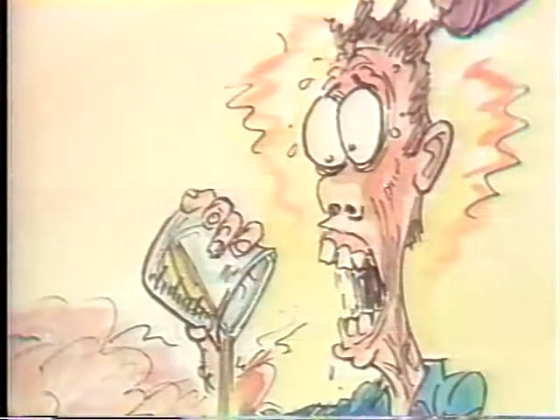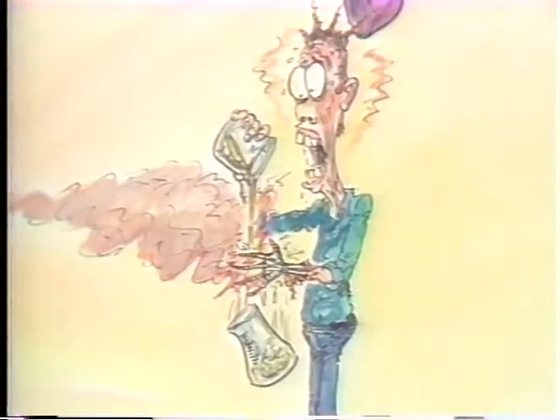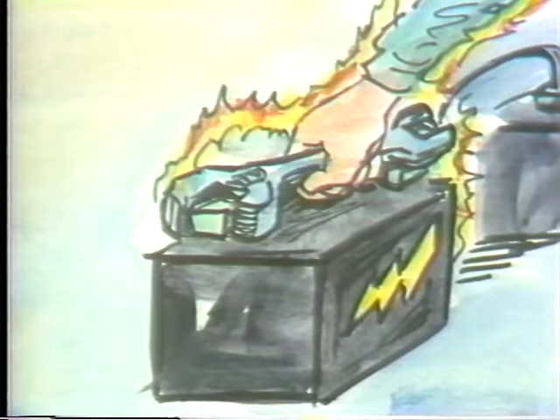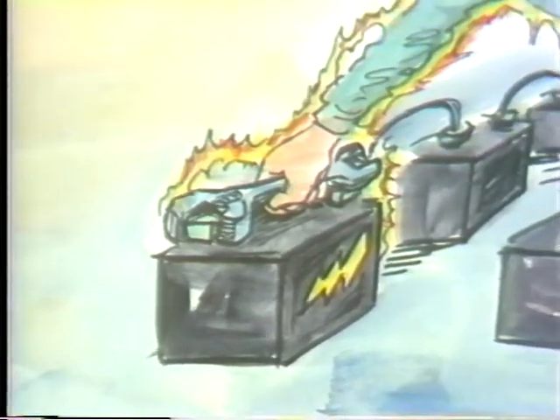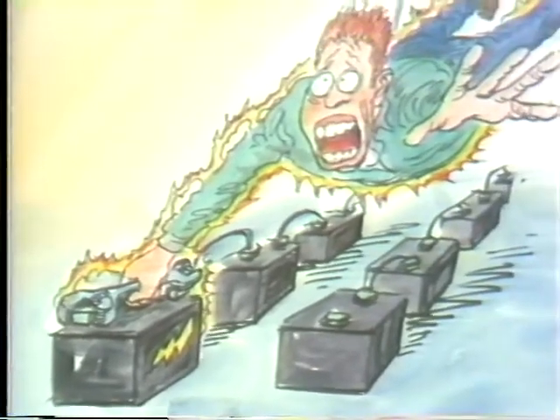Now, I'll admit that soldering isn't the most exciting job you could hope to see, but then no maintenance job is that exciting. That is until something goes wrong. Think of the possibilities right here in the battery room. Batteries like these give off hydrogen gas as a byproduct, and it just so happens that hydrogen gas is explosive when mixed with air. Unless you want this kind of excitement, don't smoke near batteries, and use only sparkless tools when working nearby. Batteries also contain acid, which is corrosive to skin and other nice things you might want to keep. Chemicals like this deserve a little bit of care in handling. Of course, there's also a shock hazard. Batteries this size generate enough juice to kill a man, so it's to your advantage to avoid carrying metal objects when you're working around them.